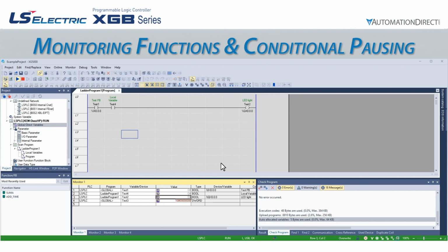Test1 and test2 won't show the value change when we edit them. If we look at the device/variable column, we see that test1 is tied to an input direct variable. And if we look at the logic in our program, we see that test2 is the output of a rung of logic. The PLC is controlling test1 based on the input status, and it's controlling test2 based on the logic state of the rung controlling it.